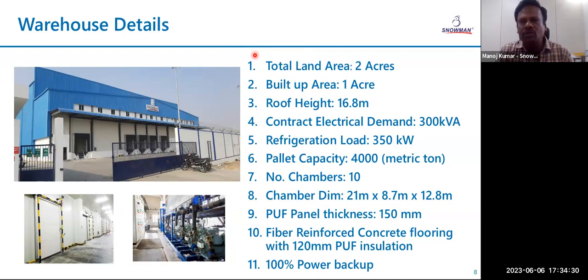The complete warehouse height is 16.8 meter, 17 meter. Every warehouse will have a 300 to 350 electrical contract demand, which depends upon our refrigeration load. The refrigeration capacity would also be 350 kilowatt. We say pallet capacity, which is nothing but storage capacity in ton. One pallet is 1 ton.